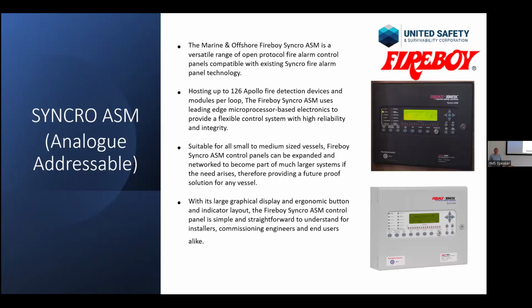Then we move on to a little bit more complicated fire detection panels. This is an analog addressable 2-loop panel. You probably come across those only on the bigger pleasure boats and some commercial vessels where you really want to know each detector's position, location. It uses a protocol that allows you to name and see the position of every detector. It's got 2 loops. The panel communicates with each device every couple of seconds, so it's very good for fault finding. You can do lots of cause and effect programming on the panel.